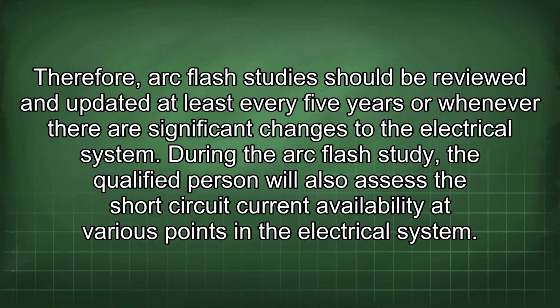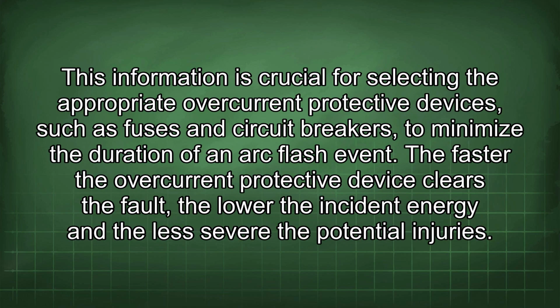at various points in the electrical system. This information is crucial for selecting the appropriate overcurrent protective devices, such as fuses and circuit breakers, to minimize the duration of an arc flash event.